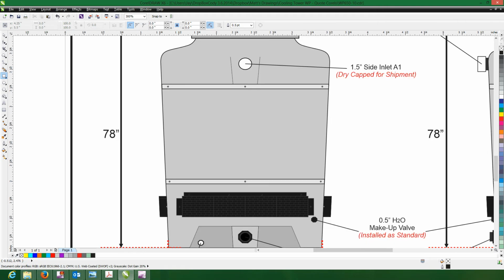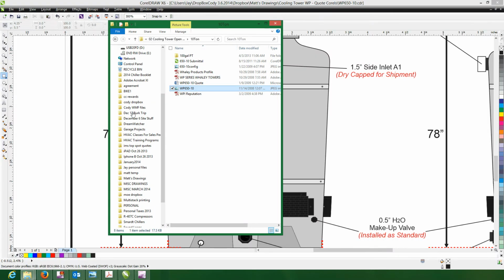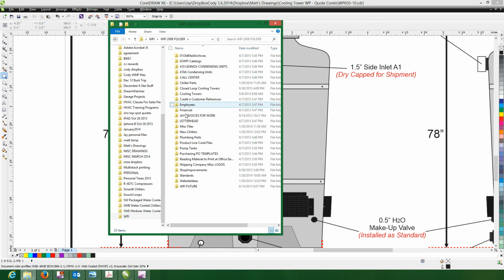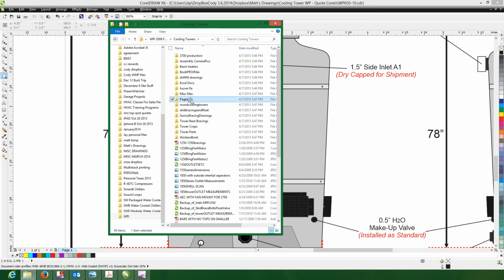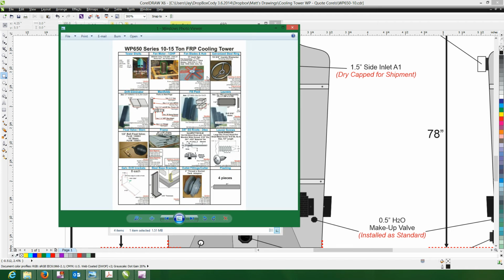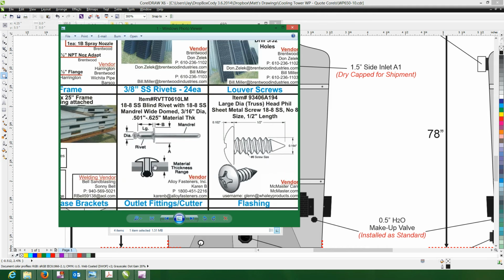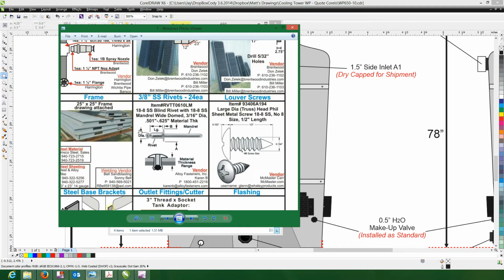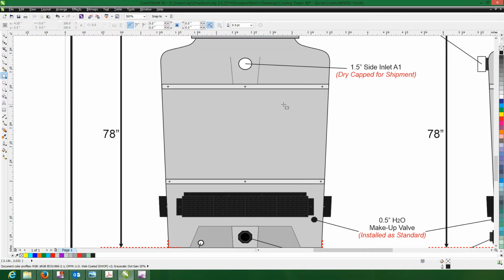If you go to the cooling tower folder — I'll show you where this is — go to WP, then WP 2008 folder, then cooling towers, then pages, then 650, and open that up. Zoom in here and you see this is a rivet, like what they use on airplanes and aircraft when manufacturing. We use a 3/16 inch rivet as a standard for these sections on the exterior of the 10 ton through 25 ton, which is 650 and 850.